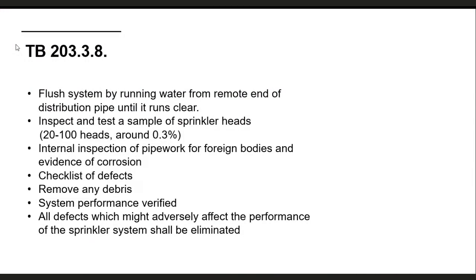You could turn a zone off, drain a zone and take the heads from there. You could use a freezing kit to remove the heads and then put a new head in or put a plug in. There are lots of different ways to do it, but it's often going to cause some disruption - the sprinkler system will be either down or compromised for a period while those heads are removed. Once removed, we send them off to a lab or body to do those tests. I'll come on to that later.